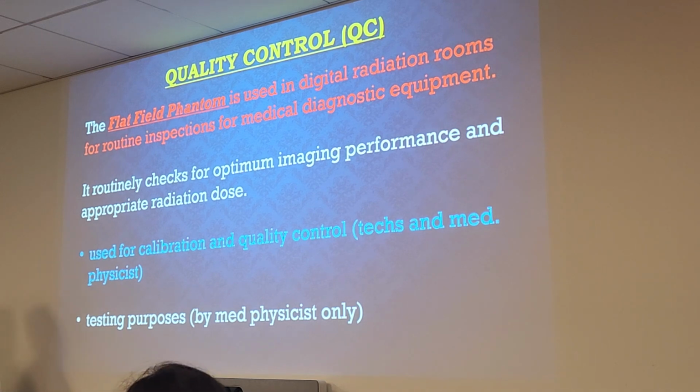Yes. So, when Cody and I were at TSRT last year, we had a chance to talk to a vendor tech guy. He talked about phantoms, and they were for learning purposes as well as inspection. Like, let's say he had a fake arm, you would sit that on a detector, X-ray it, and you expect the image to come out a certain way. Is that what you're talking about here?